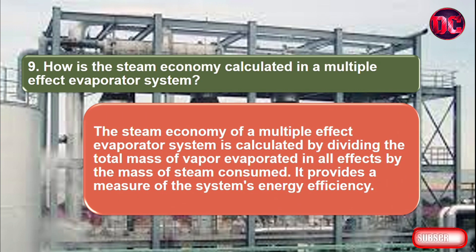How is the steam economy calculated in a multiple effect evaporator system? The steam economy is calculated by dividing the total mass of vapor evaporated in all effects by the mass of steam consumed. It provides a measure of the system's energy efficiency.